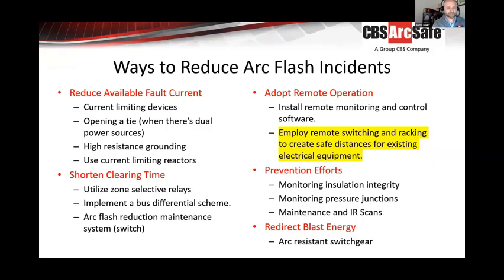If your electrical switchgear isn't maintained or is out of date, if it's operating on, let's say, a trip slower than it should, then that arc flash label on your switchgear is probably pointless. Because if we think it's operating slower than it should to trip something, then that arc flash calculation can go up exponentially. So you have to maintain your equipment.